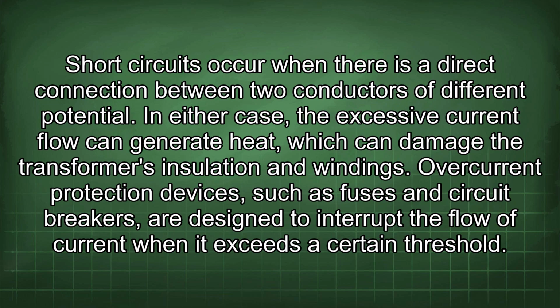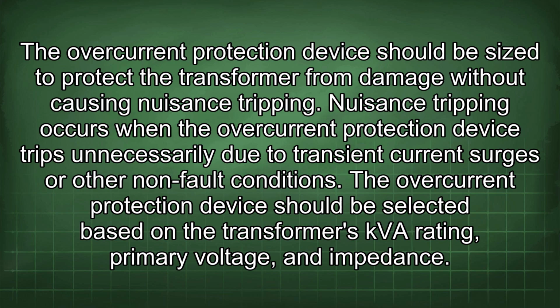In either case, the excessive current flow can generate heat, which can damage the transformer's insulation and windings. Overcurrent protection devices, such as fuses and circuit breakers, are designed to interrupt the flow of current when it exceeds a certain threshold. The overcurrent protection device should be sized to protect the transformer from damage without causing nuisance tripping. Nuisance tripping occurs when the overcurrent protection device trips unnecessarily due to transient current surges or other non-fault conditions.